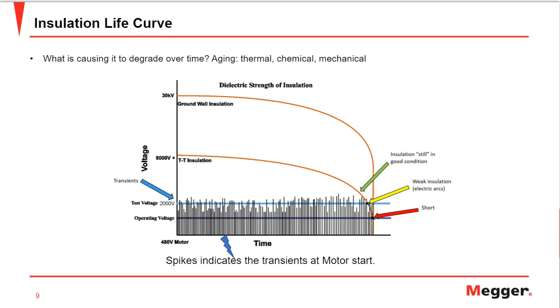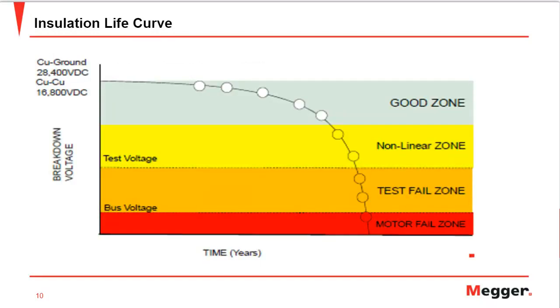So how do the DC high potential testing and surge testing help us understand where our motor lies on the insulation life? You can see on the screen we have four different zones: a good zone, non-linear, test fail, and then the motor fail zone. What we are trying to avoid is going to this zone. As a motor operates, or is in working condition, it's in the good zone. Over a period of time, let's say a 460 volt motor, in the previous slides we've seen it's 28 kV DC to ground. Being able to determine that a motor has entered its final stage of life, or the red zone, is key to an effective electric motor reliability program.